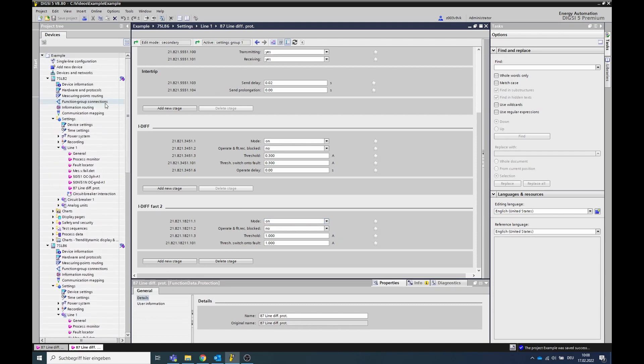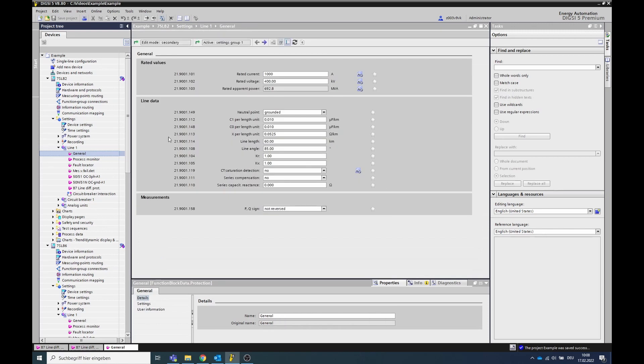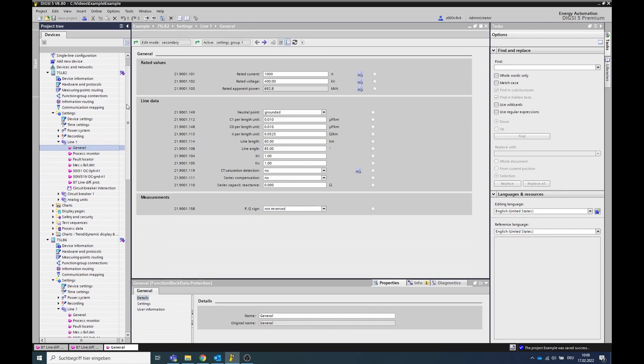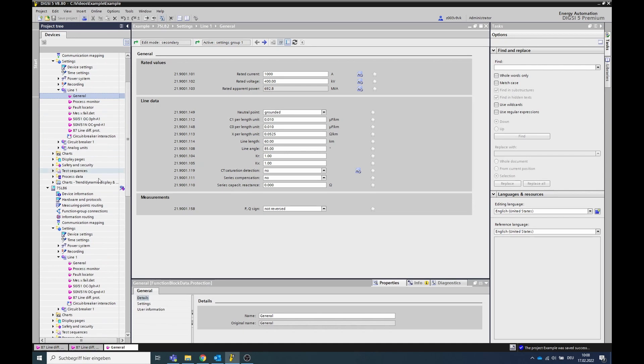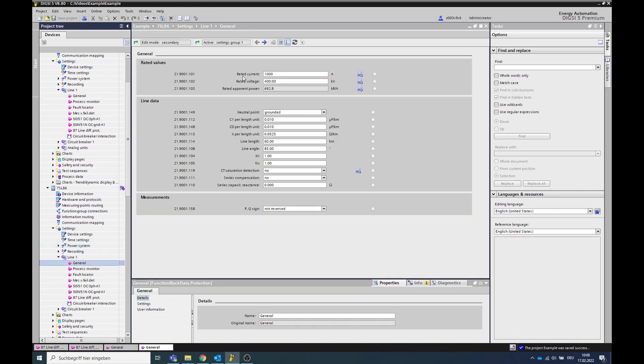Go to the line function group and open the function block general. Verify that both devices have the same primary rated current. If a transformer is in the protected area and the rated current is different, make sure that the rated power is set equally at both ends.